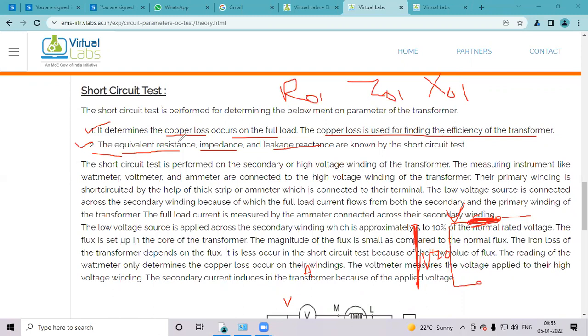Now the short circuit test is performed on the secondary or the high voltage winding of the transformer. Secondary side किंवा high voltage winding of the transformer ला perform करतो आपण. So the measuring instruments are again the same. Instead of 2 voltmeters, we require one extra ammeter. See, the wattmeter, voltmeter, and ammeter are connected to the high voltage winding of the transformer.